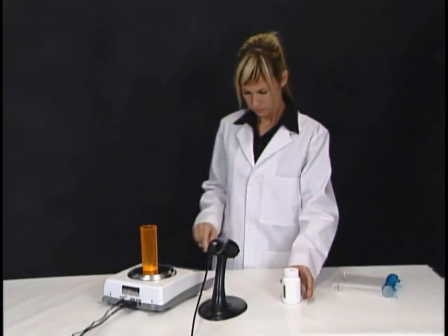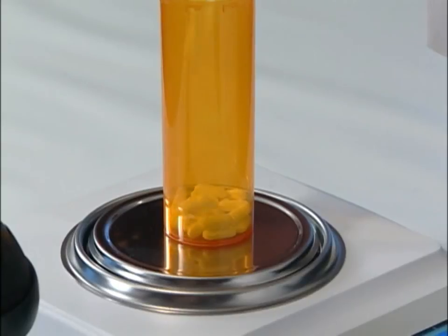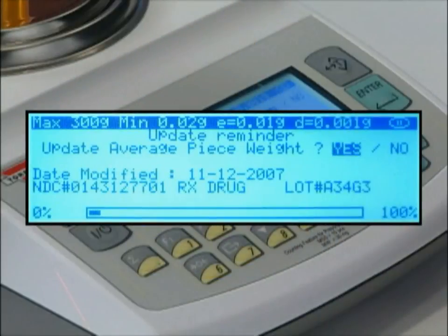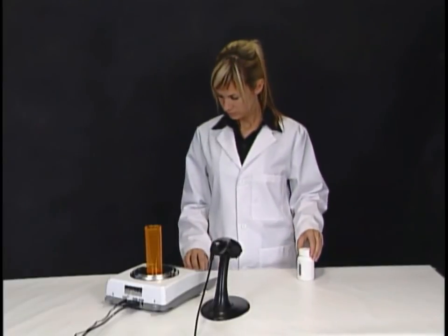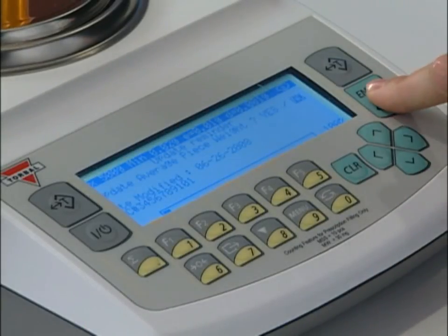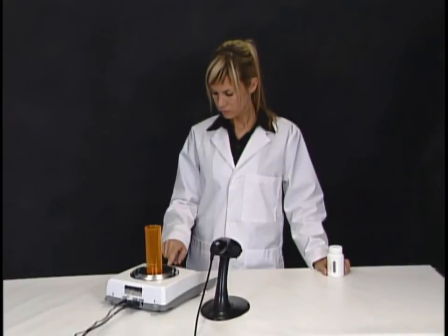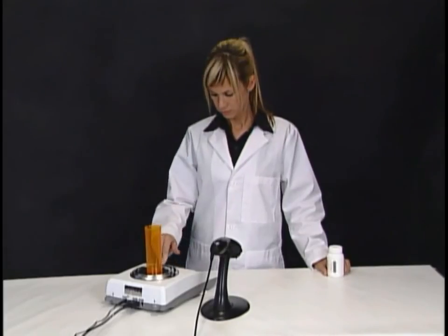You can then proceed with the remainder of your count. Maintaining the database and updating the average piece weight is also very easy. The scale's data entry reminder feature will actually remind you to update the average piece weight. After taring the vial and scanning the NDC barcode, the scale will check to see when the last update was performed. If more than 30 days has passed, a reminder is displayed. You can then update the drug's information as part of your counting process or ask the scale to remind you later. Depending on your application, the reminder can be set for 30, 60, or 90 days. Average piece weight can also be updated anytime with the use of the sigma key.